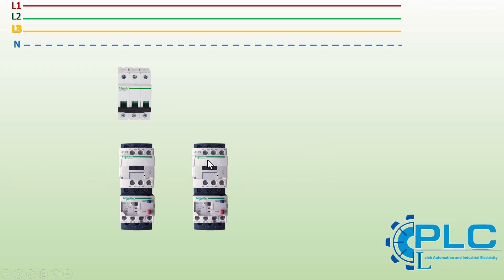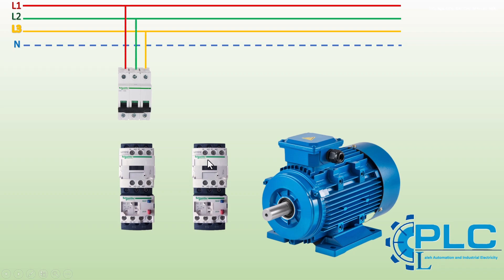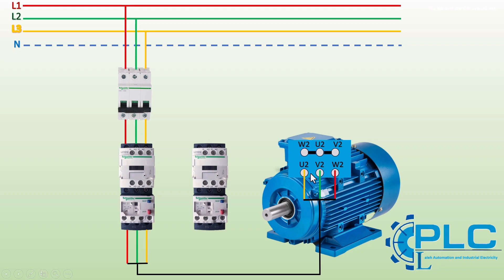Let's start with the power circuit wiring. First, I connect the three-phase power supply to the input terminals of the first contactor. Then I connect the output of the first contactor to the motor terminals. Now, for the second contactor, we need to swap two of the phase wires — for example, we can swap phase two and phase three. It doesn't matter which two phases you swap, and you can do this on either the input or output side of the second contactor.